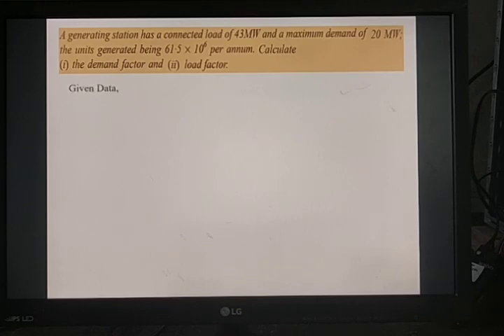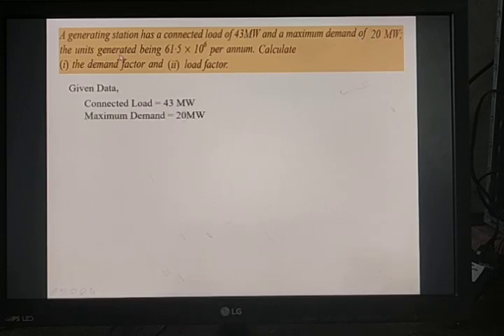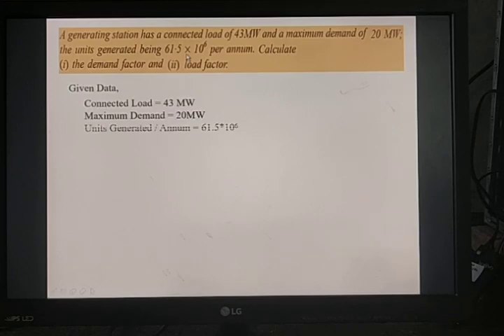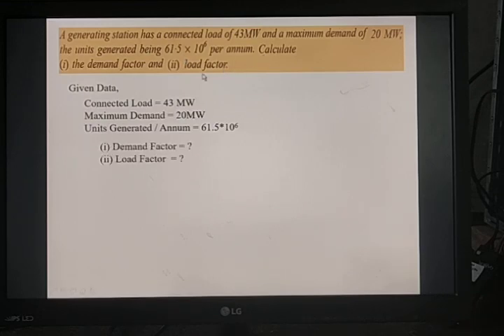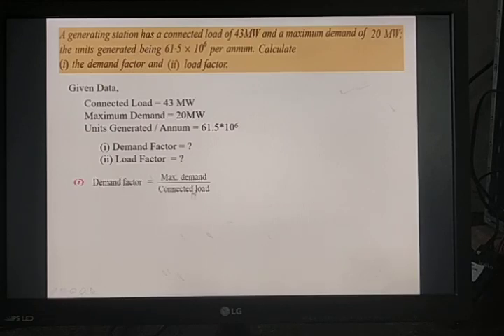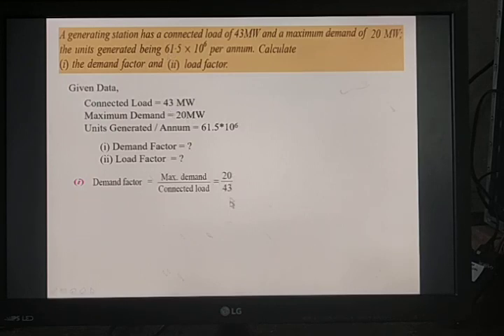Given data: connected load is 43 megawatt, maximum demand is 20 megawatt, and units generated per annum is 61.5 × 10⁶. We need to find two parameters: demand factor and load factor. The demand factor is defined as the ratio of maximum demand to connected load, which is 20/43 = 0.465.